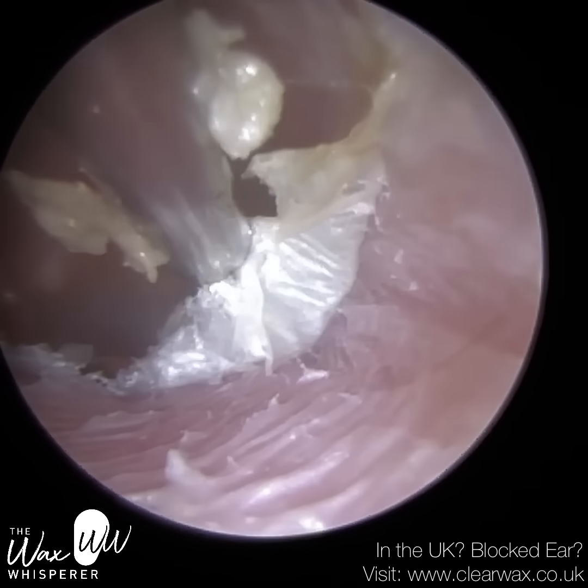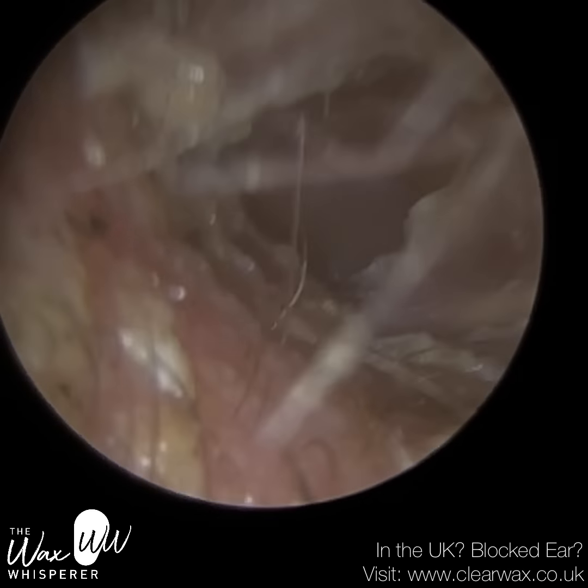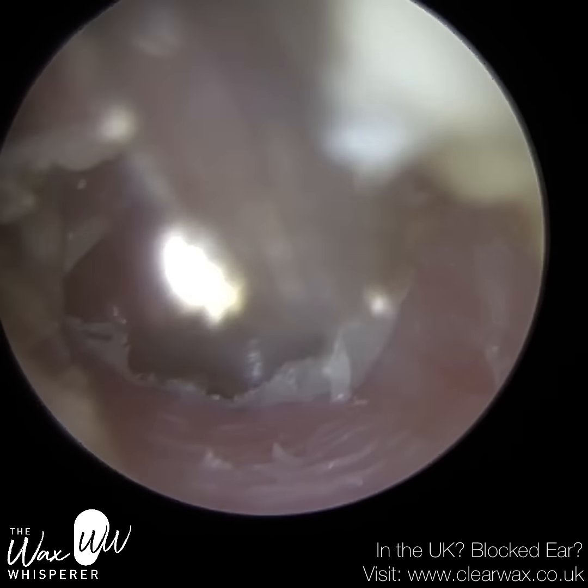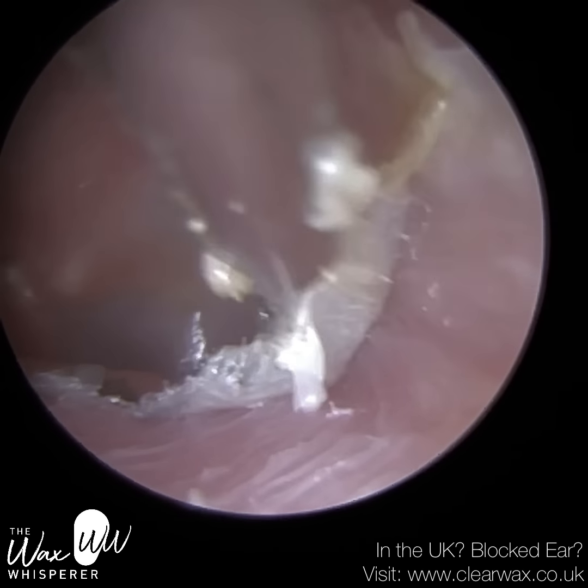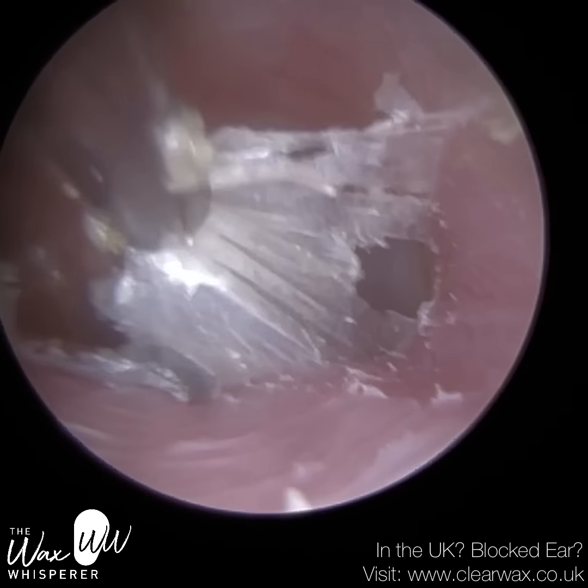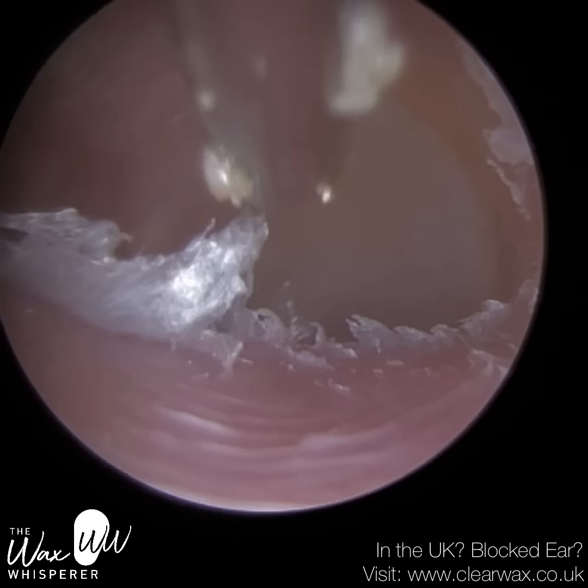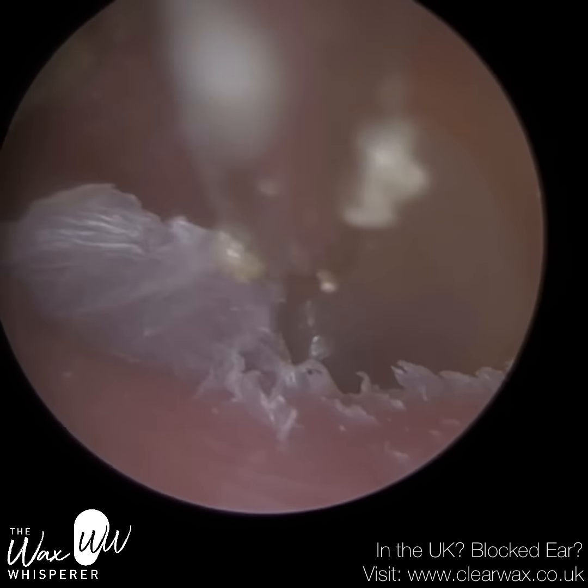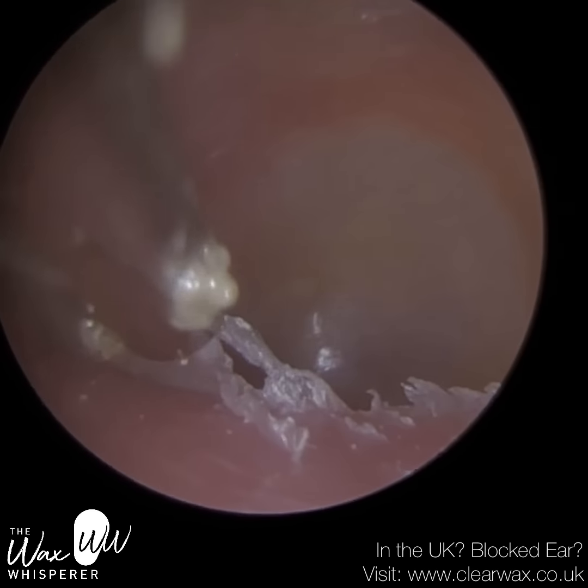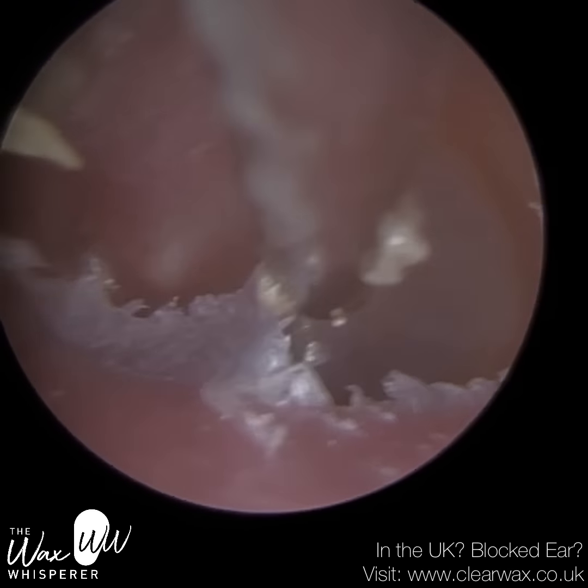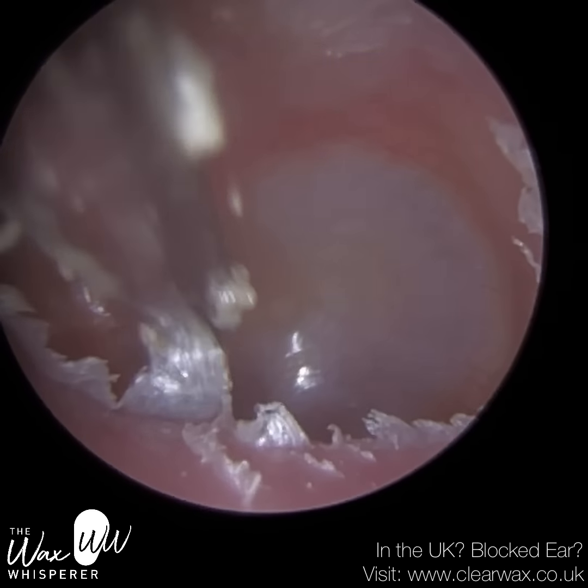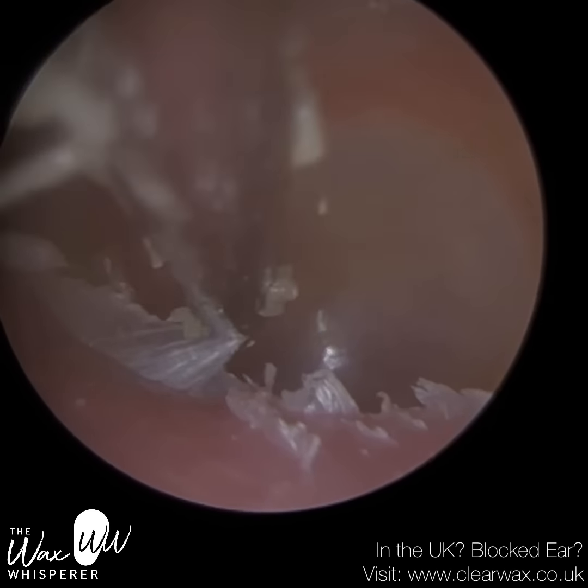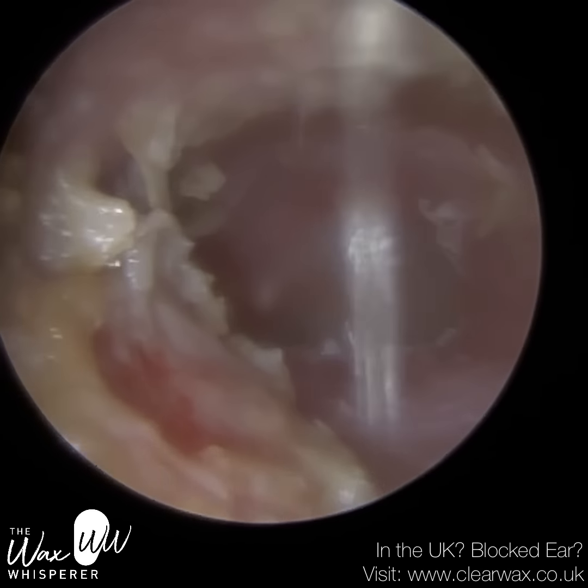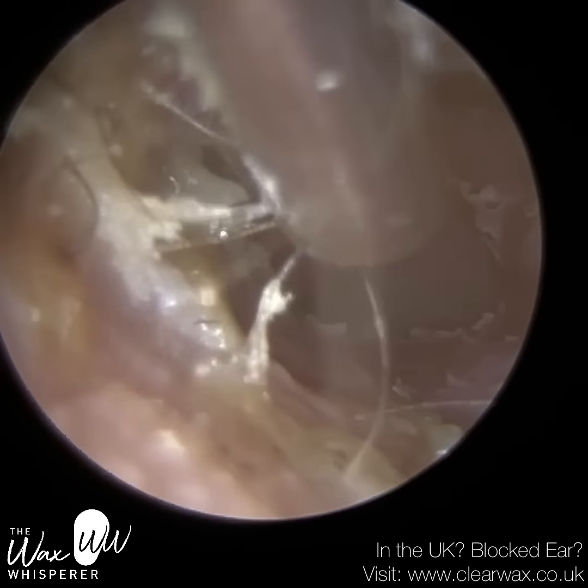But even if I didn't have the sucker, if I just left the endoscope, this is one of the really great advantages of an endoscope compared to a traditional otoscope, for example, that may go in the ear, is with an endoscope, the rod lens system, so it's almost like a telescope. If you think about a telescope, it's a long piece of like a steel rod lens that enters the ear, and ours is about 5 centimeters in length. Surrounding the optics in that rod lens system is a series of optical light fibers, and that's what transfers the light into the ear and also transfers the image back from the ear into the endoscope, which is then viewable via the eyepiece. And those optical light fibers, they obviously conduct heat from the light source, so the kind of the torch, the light that we illuminate into the ear, they travel up and through these optical light fibers, and because they're surrounded all the way around the endoscope, the heat from the light is evenly distributed.